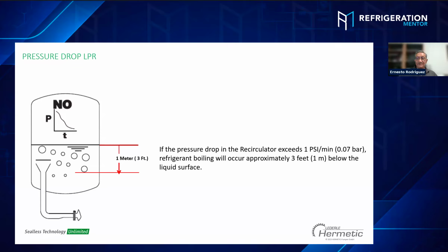CO2 is more critical because CO2 has the tendency to flash more versus ammonia. But ammonia is still bad too, right? If you pull it down too fast, yes, that's still going to make bubbles go into the motors. You're dropping the pressure too fast in the vessel, you see these bubbles, and that's going to start cavitating that motor. You may not kill or damage the motor right then, but that does damage.